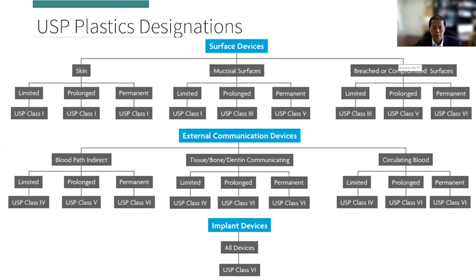I won't go through all of these in detail, but essentially USP testing is typically not sufficient as a standalone for assessing medical device biocompatibility, although it is commonly used to designate a raw material as safe for use in manufacturing medical devices. Typically, regulatory agencies will not accept just a USP certificate in lieu of international standards testing, which I'll be talking about shortly.